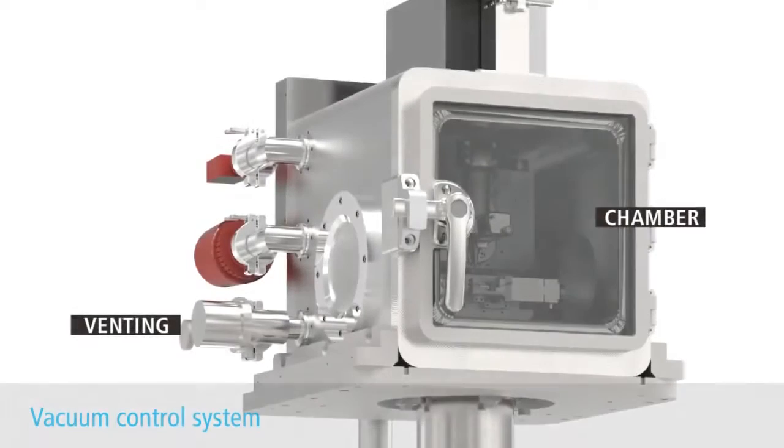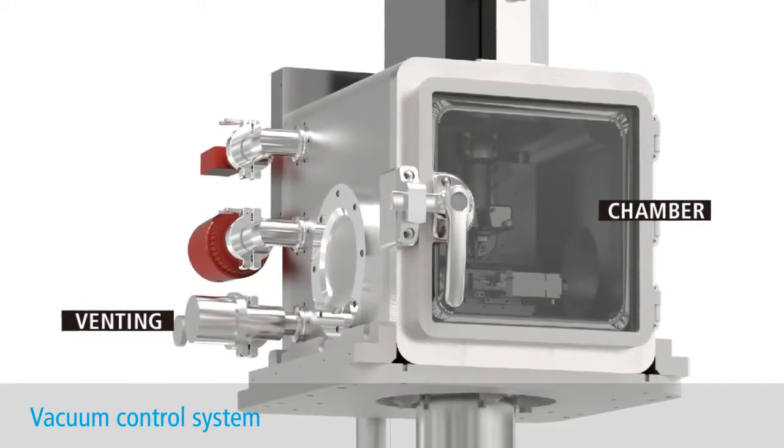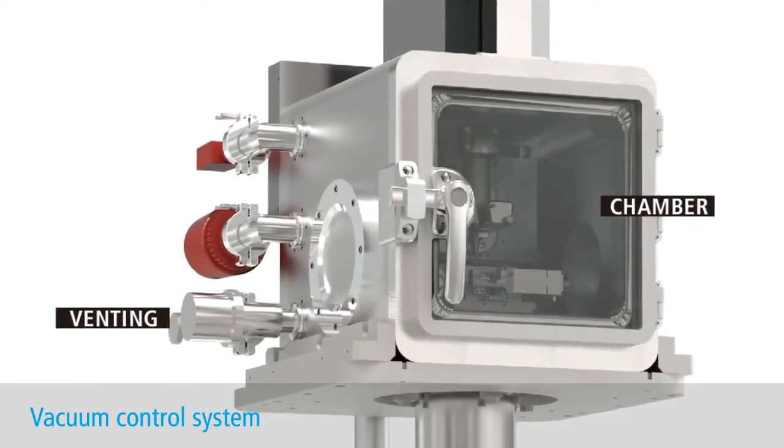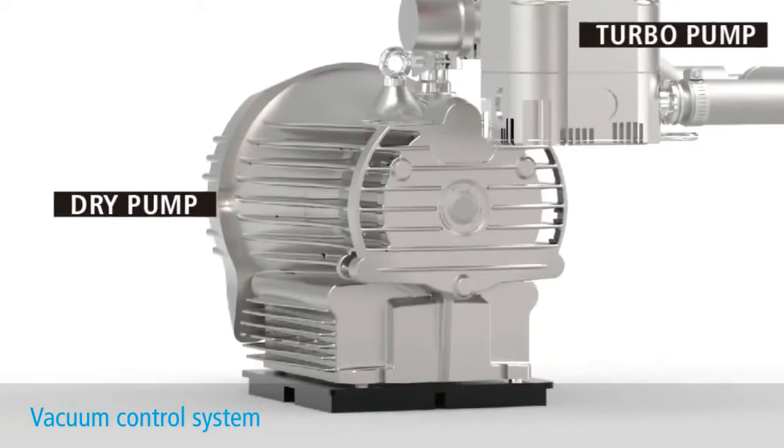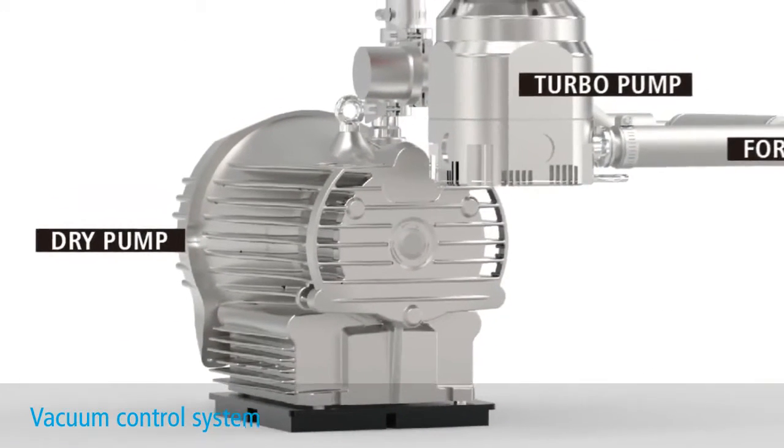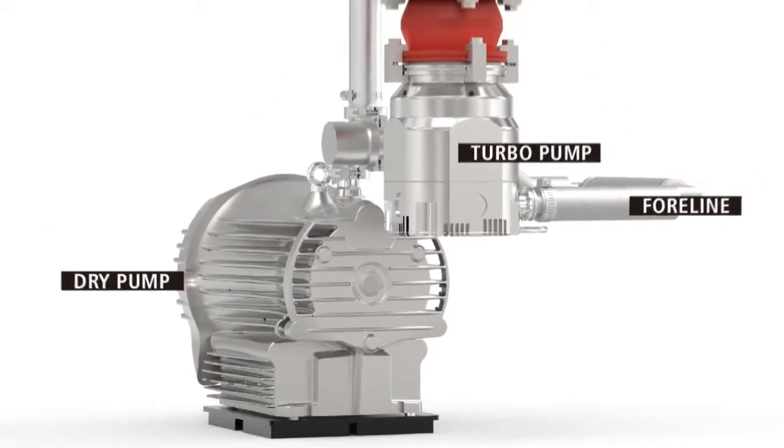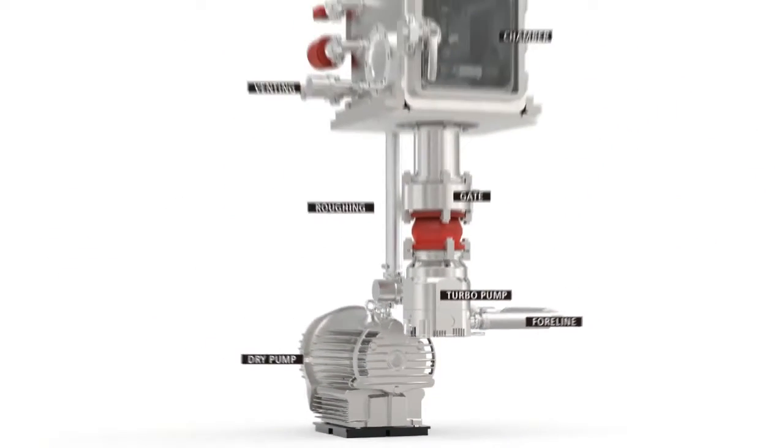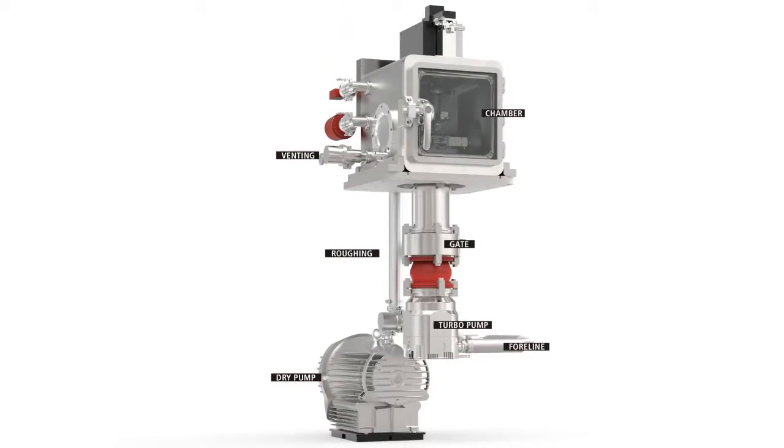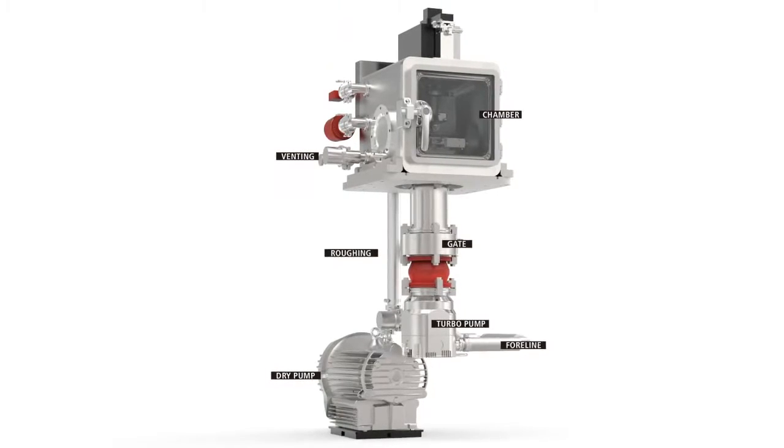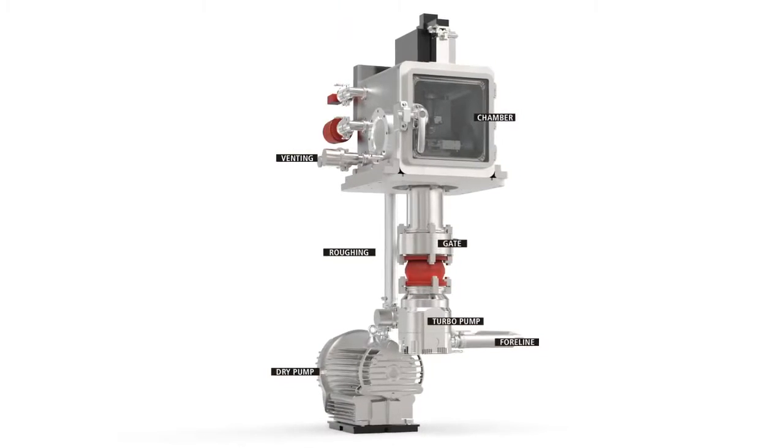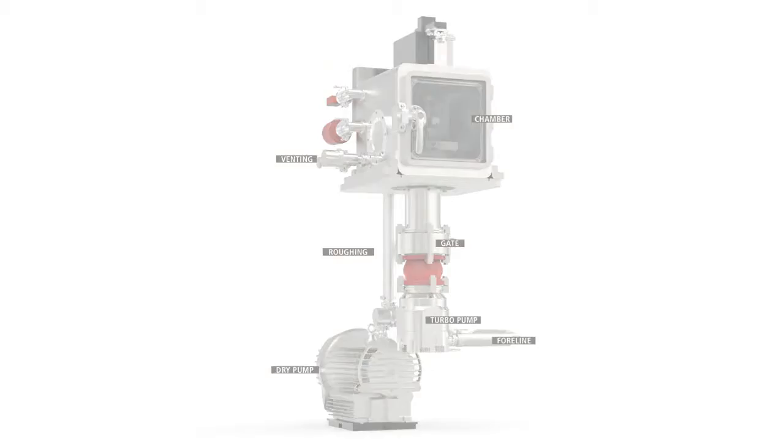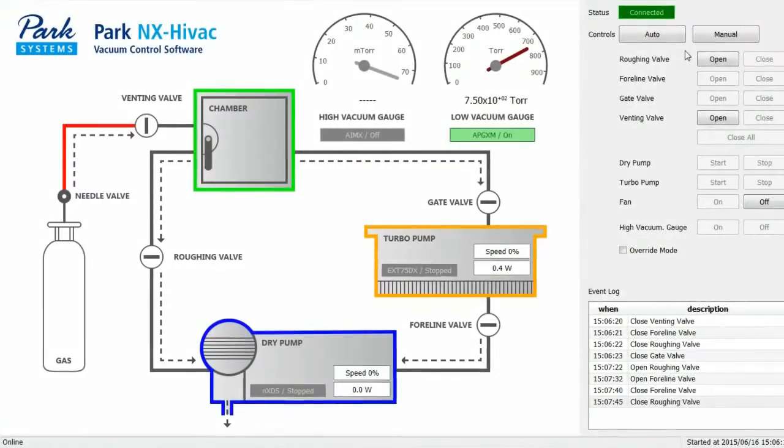Moving on, we have the vacuum control system. The high vacuum is controlled by turbo and dry pumps installed here under the system panel. One noteworthy advantage of this design is that the pumping will not affect system noise levels during sample imaging.